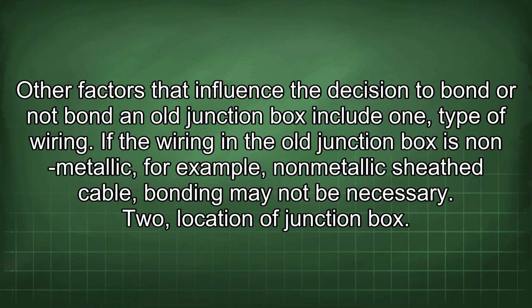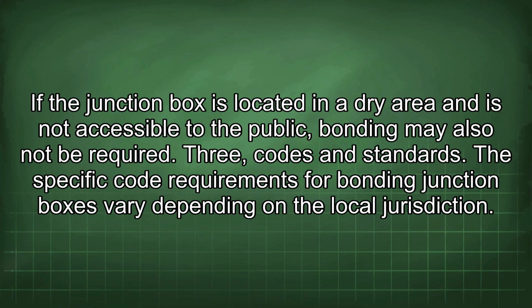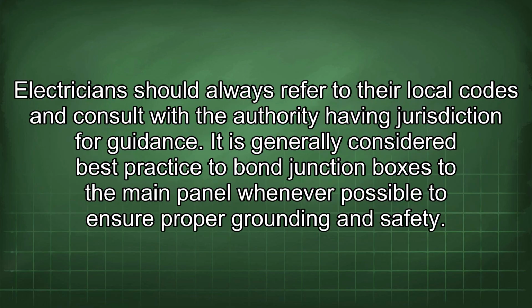Other factors that influence the decision to bond or not bond an old junction box include: 1. Type of wiring. If the wiring in the old junction box is non-metallic, for example, non-metallic sheathed cable, bonding may not be necessary. 2. Location of junction box. If the junction box is located in a dry area and is not accessible to the public, bonding may also not be required. 3. Codes and standards. The specific code requirements for bonding junction boxes vary depending on the local jurisdiction. Electricians should always refer to their local codes and consult with the authority having jurisdiction for guidance. It is generally considered best practice to bond junction boxes to the main panel whenever possible to ensure proper grounding and safety.